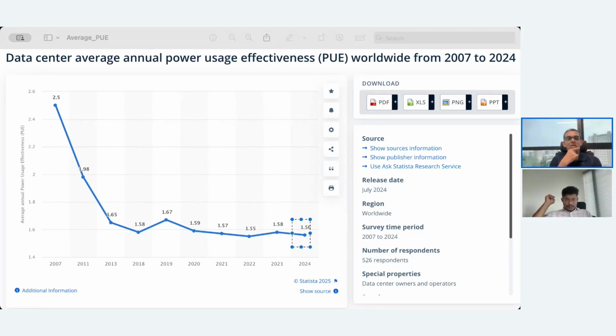Sometimes, in our experience - Anurag can help me with his views here - while measurement systems, sensors etc. are installed, the computation of PUE doesn't take into account a level 3 measurement. It might be taking it at the PDU level or at the UPS level. That's what our experience is.